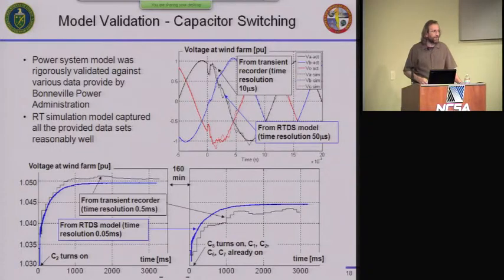This slide illustrates how accurate the model was. On the lower left, you see a capacitor bank switching event recorded with a transient recorder. The black line is what the transient recorder produced when a capacitor bank was switching at the wind farm. When you switch a capacitor bank, the voltage typically goes up a bit because you provide VARs into the system, and you see the black line going up. In about 1 second, you reach about a 2% increase in voltage. The blue line is from the RTDS simulation, which very nicely captured that.